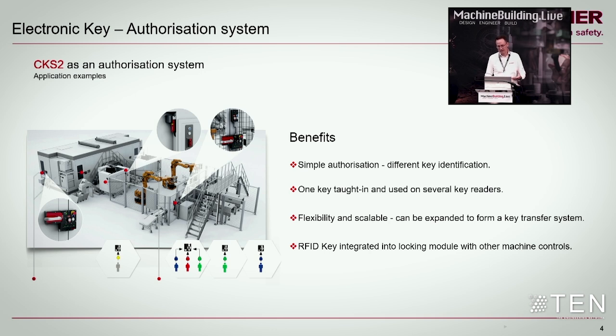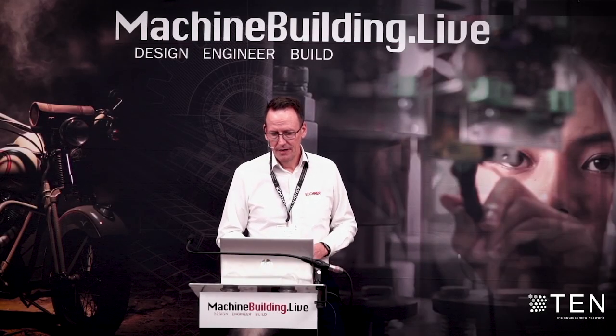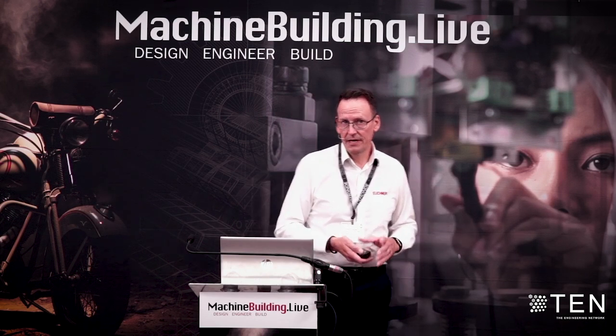The benefit there is that you've got a simple authorization. You can have different keys for different parts of the cell. They can be in different colors if you need to. And if you lose them, it's a very simple teaching facility. I say simple, you need to go into the software and it's a deliberate action to reteach a new code, but the previous key is forgotten. And you can program, if you want to, several read keys, so you might want more than one key to be in existence. So as an authorization system, it's very flexible, and it can form part of a key transfer system.